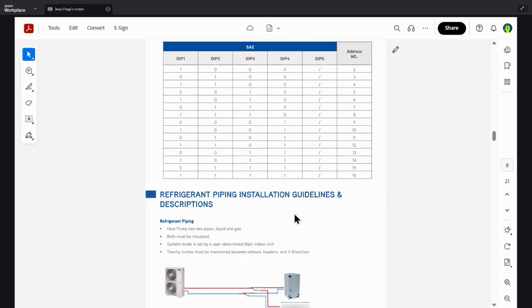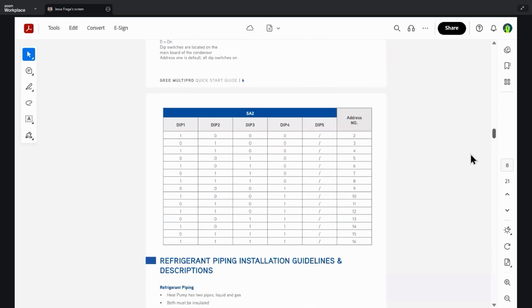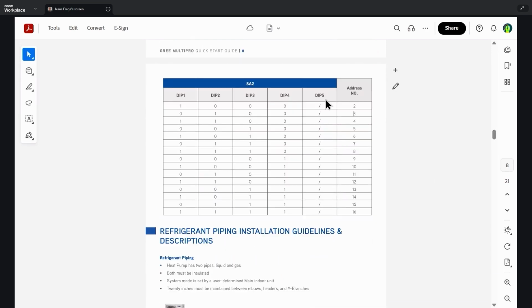Going on forward here, this is the chart that I was referencing. So we know that system 1 is going to have all the dip switches in the off position. System 2 will have dip switch 1 in the on position. System 3 will have dip switch 2. System 4, 1 and 2, and so on and so forth, depending on the unit that's in line in your daisy chain.